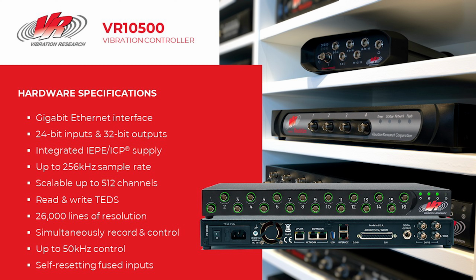The back of the VR10500 also features those outputs on the right hand side. It also features, just like the 9500, an aux inputs and outputs for that digital and analog communication with other pieces of equipment. And then next to the aux inputs and outputs is the interbox option for connection to the PC, and they also will daisy chain together that way.